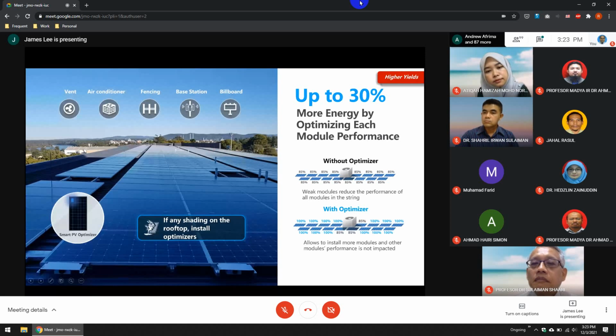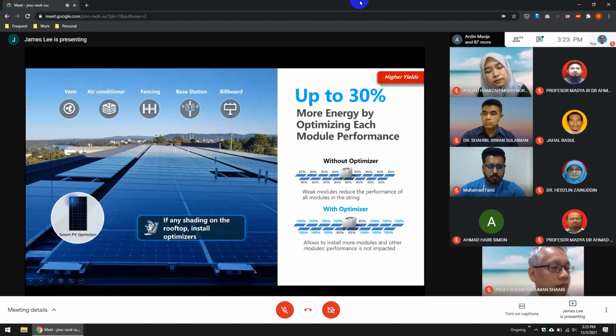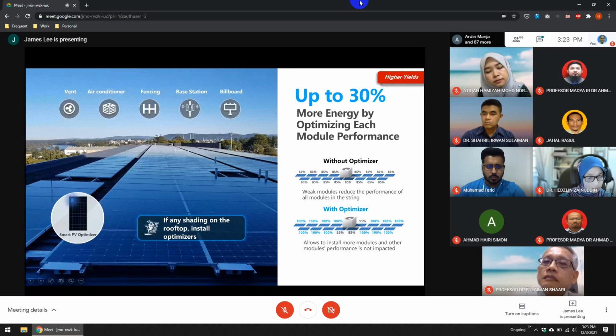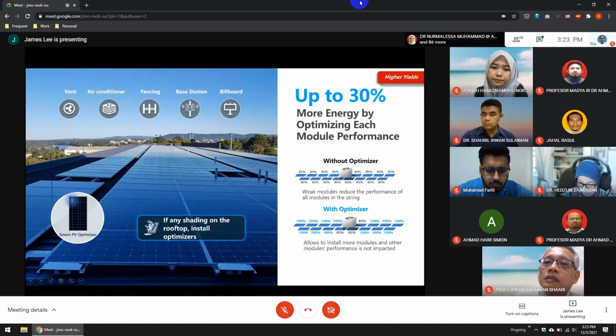As the day goes on, the shadow may move closer. Optimizers let you fully segregate the performance of panels down to the individual module level. Without optimizers, there's aggregation across all the strings connected to a shaded module. With optimizers, the rest of the panels perform optimally to their conditions, while only the shaded ones are impacted accordingly.